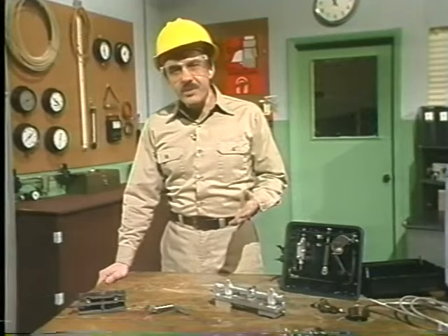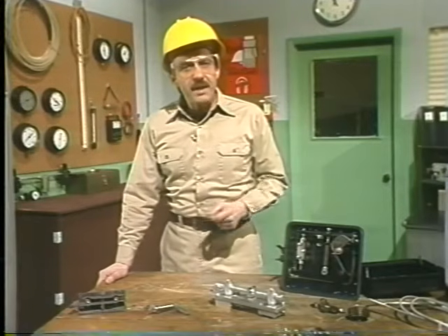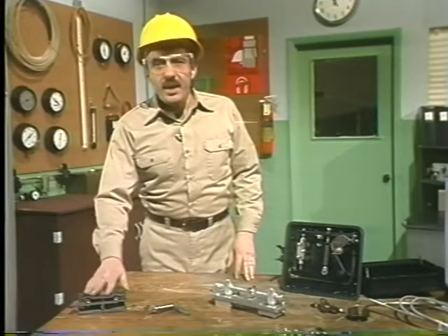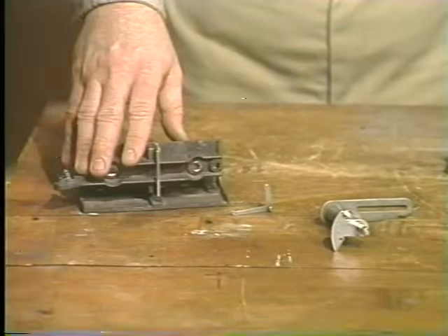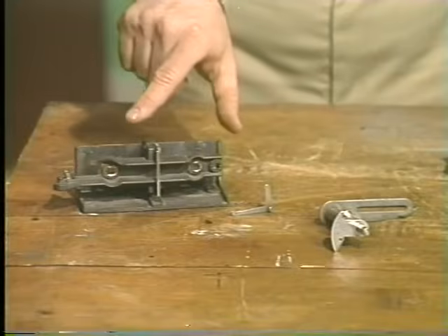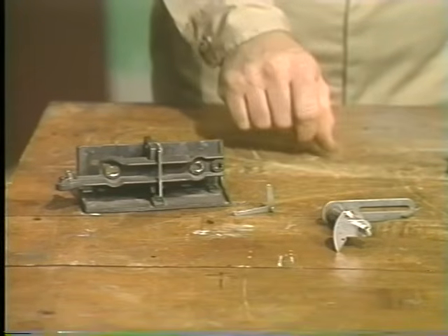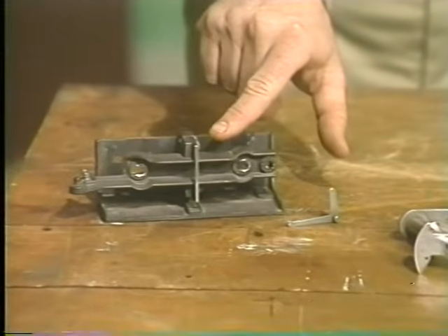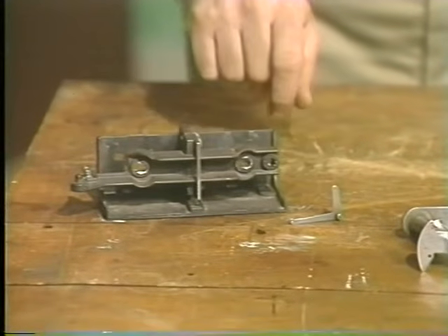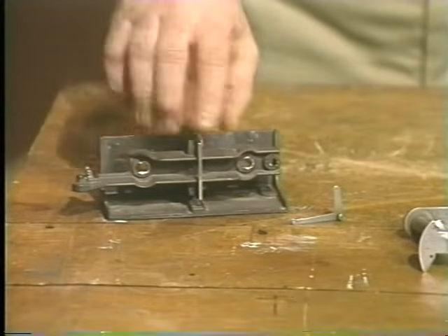Now, the examples we've seen of levers are okay as far as that goes, but you're more likely to find levers like these in pneumatic instruments. Now, these levers can be divided into two categories: two-sided and one-sided. Both of these levers are two-sided. They belong to the first group of levers because the pivot is located between the effort and the resistance.